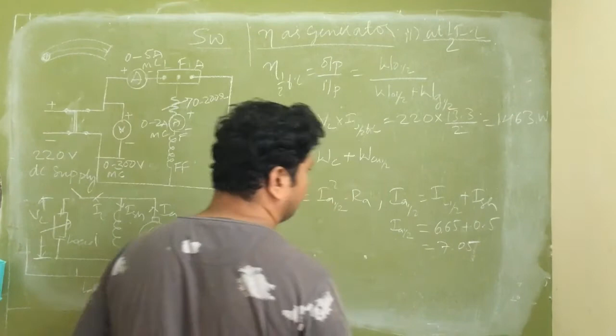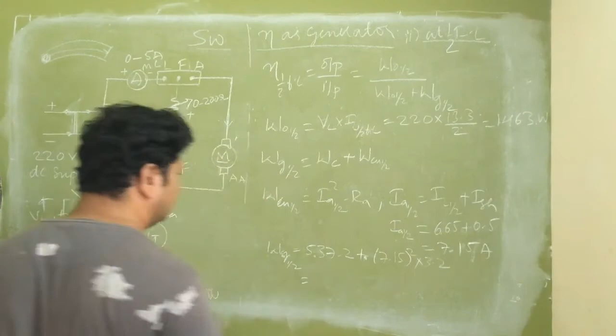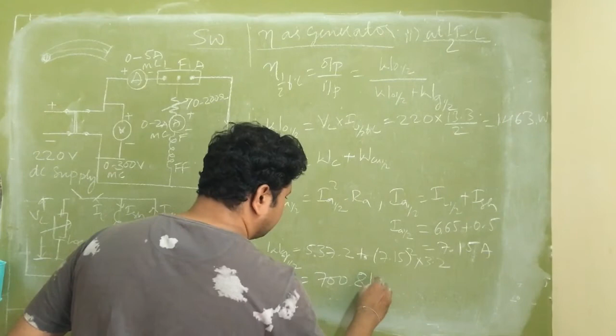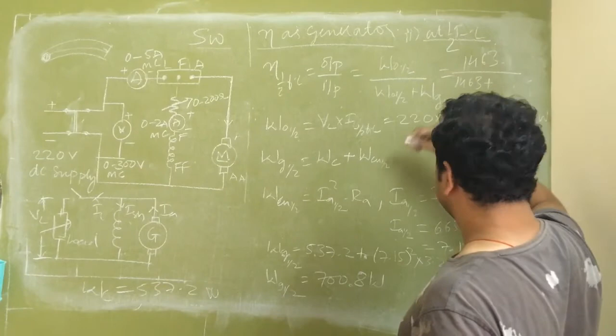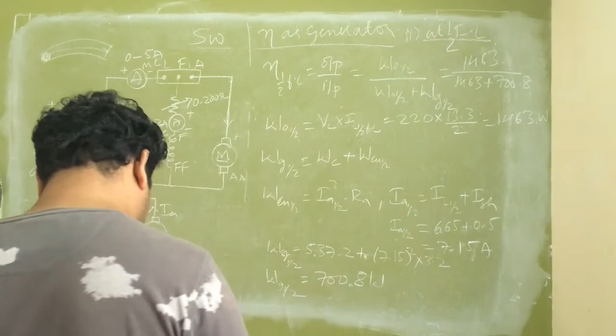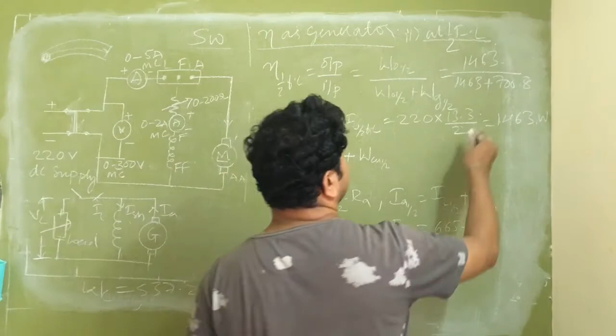Now using this you calculate the losses. Wg at half the full load: constant loss is the same, 537.2, plus 7.15 square into 3.2. It is 700.8 watts. This is Wg at half. Now what is the efficiency? Efficiency at half the full load equals output 1463 divided by 1463 plus 700.8, which is 67.6%.